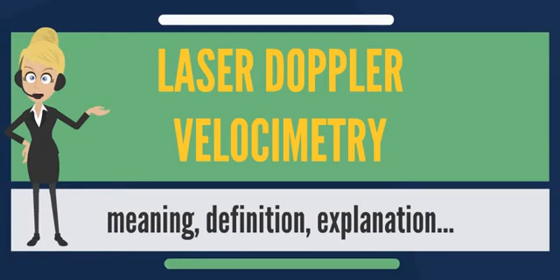Laser Doppler Velocimetry (LDV), also known as Laser Doppler Anemometry (LDA), is the technique of using the Doppler shift in a laser beam to measure the velocity in transparent or semi-transparent fluid flows, or the linear or vibratory motion of opaque, reflecting surfaces. The measurement with LDA is absolute, linear with velocity, and requires no pre-calibration.